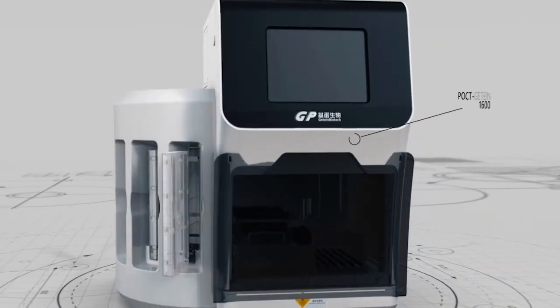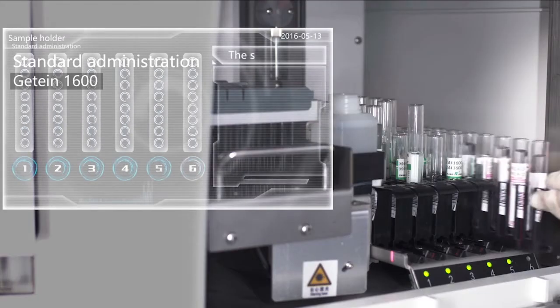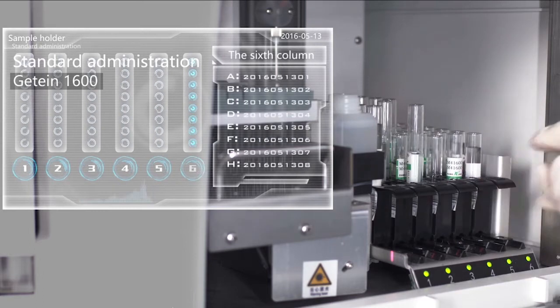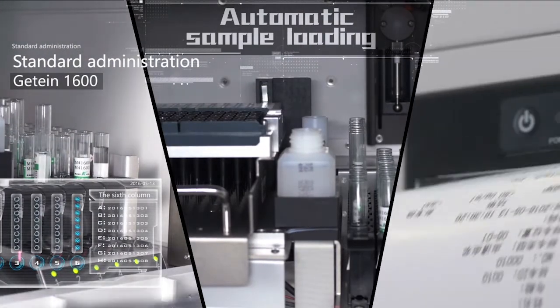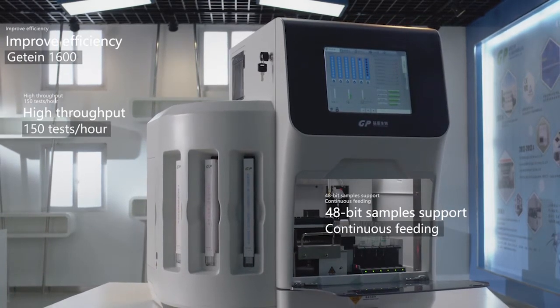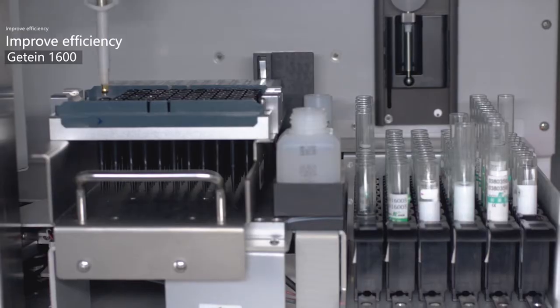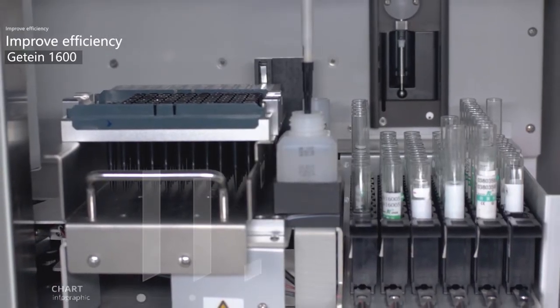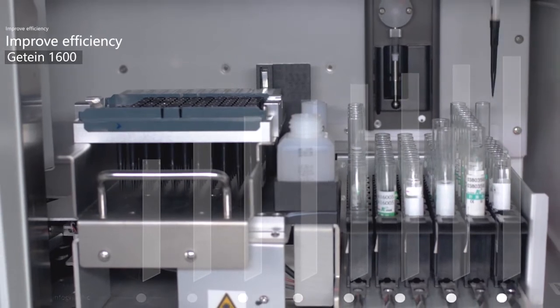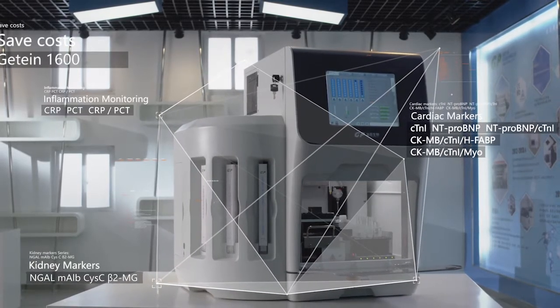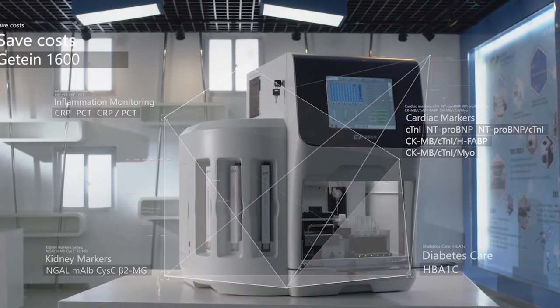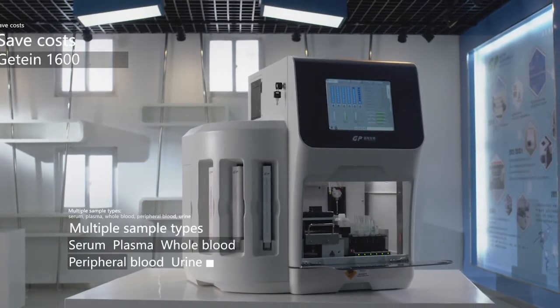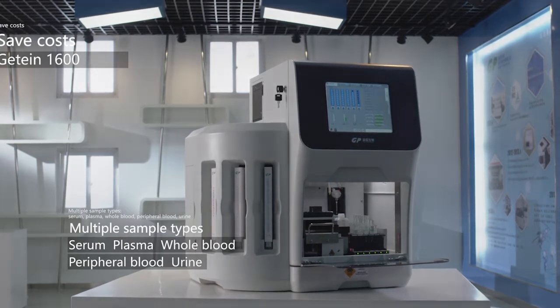Getein 1600 employs an automatic testing system which could automatically run the tests without too much human intervention. The instrument has three loading ports for strip holders, and each holder contains either 48 or 24 sample cartridges. Samples could be loaded at the same time or in succession and could be tested for multiple items. The emergency mode permits the instrument to stop the auto running mode to allow emergency samples to be tested instantly.